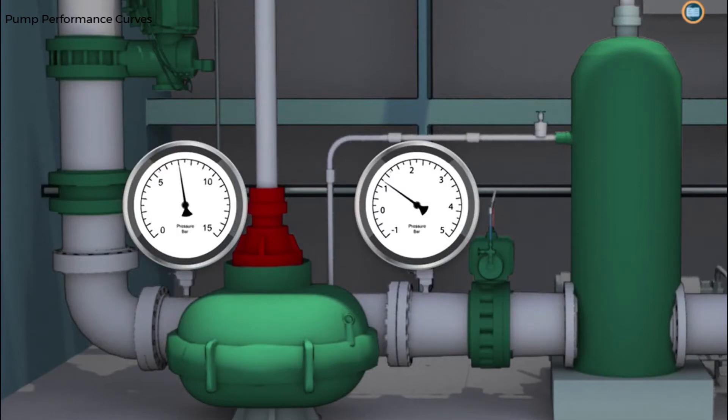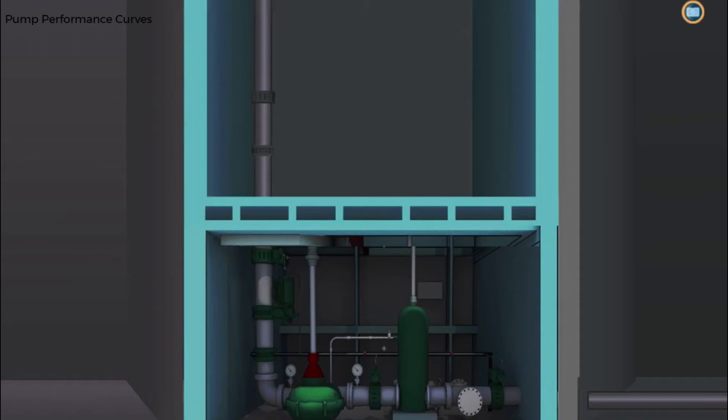If you are to control the flow of crude oil cargo correctly during bulk discharge, it's important that you understand the relationship between the flow and pressure generated by a centrifugal pump. When considering the pressure generated by a centrifugal pump, it's useful to think about how far up a column a pump can lift a liquid. Pumping system designers and manufacturers refer to this as head, or more accurately, discharge head.